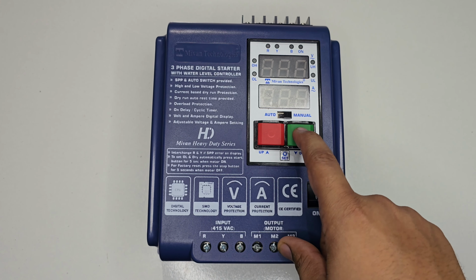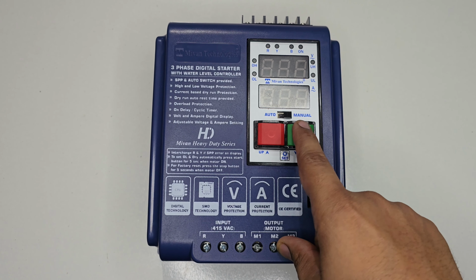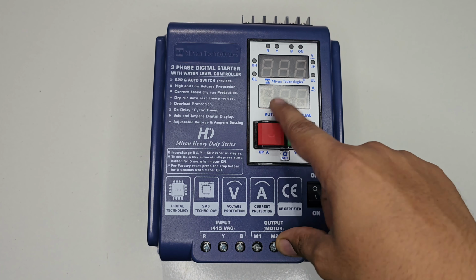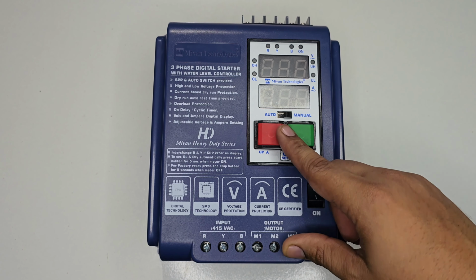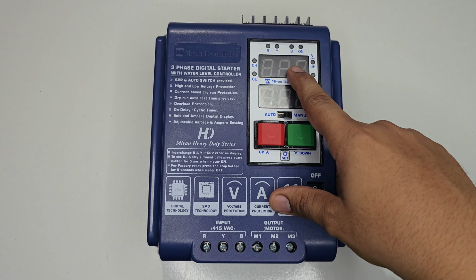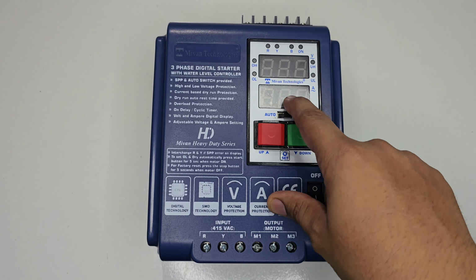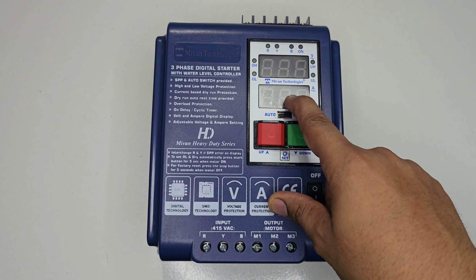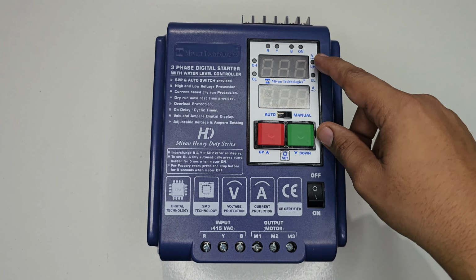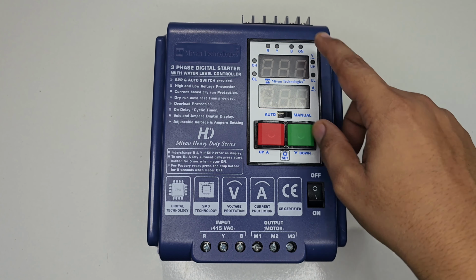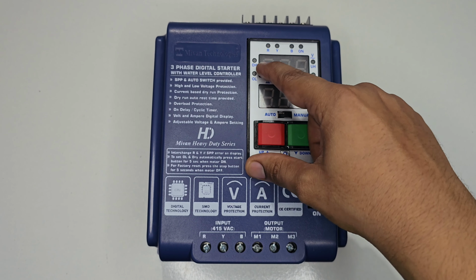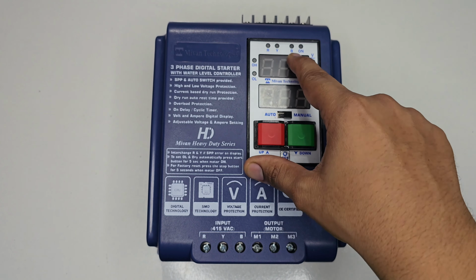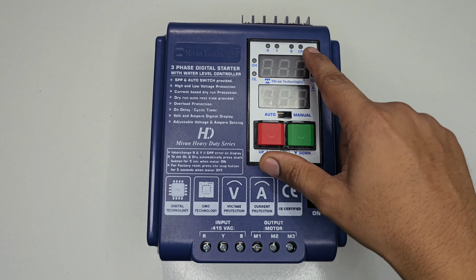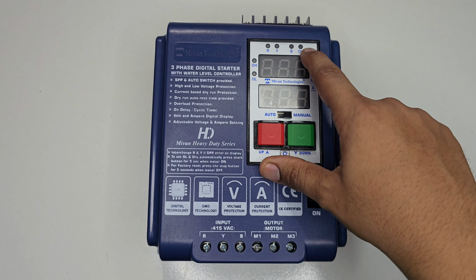These are the start and stop buttons to start and stop the motor in manual mode. This is the auto and manual switch. This upper display shows the voltage. This lower display shows the current in ampere. These are the underground tank level indications. These are the overhead tank level indications. These are the phase indications R, Y and B, and this is the motor on indication.